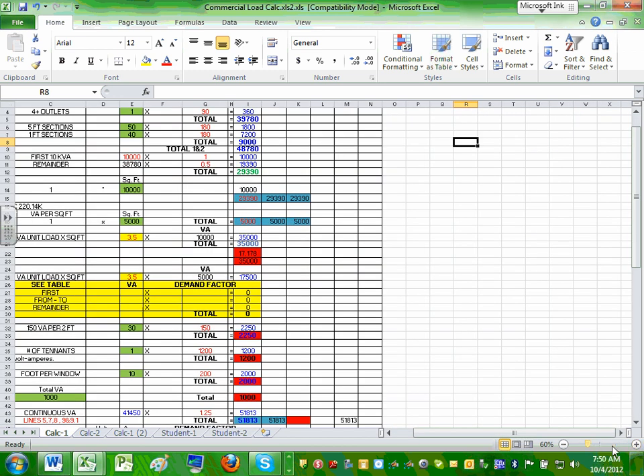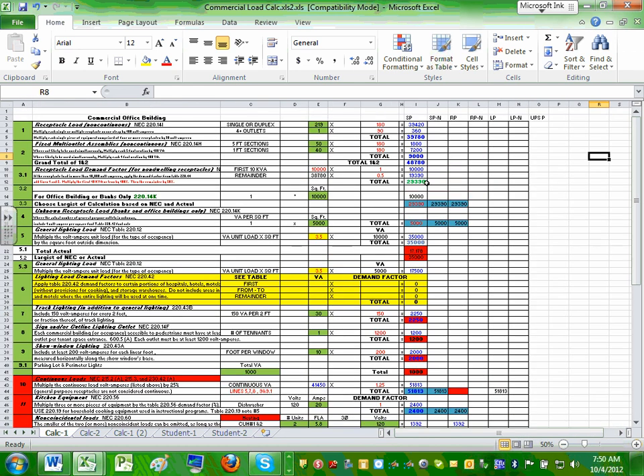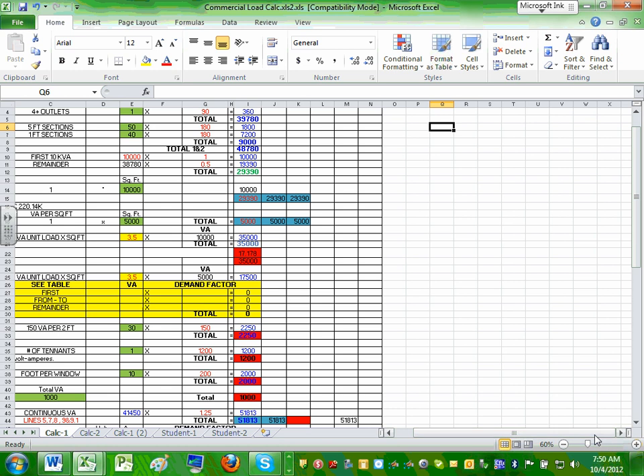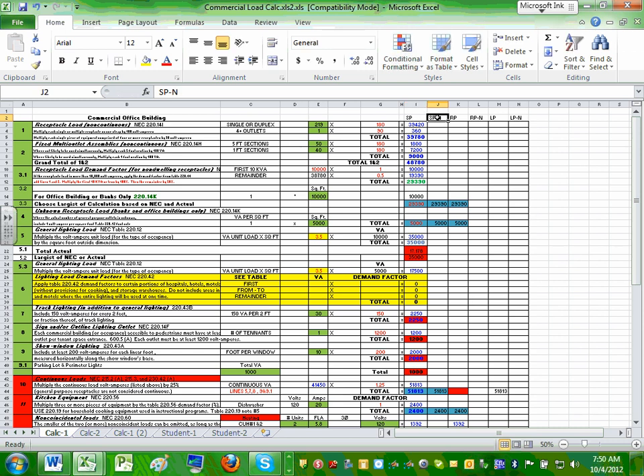Let's grab your codebook because I'd really like you guys to be with me on the codebook too. Here's what your sheet should achieve. You have the service panel — SP at the top. SPN is calculating the neutral. RP is the receptacle panel, RPN is the receptacle panel neutral. LP and LPN are the lighting panel and its neutral. These are the ones that we are sizing.